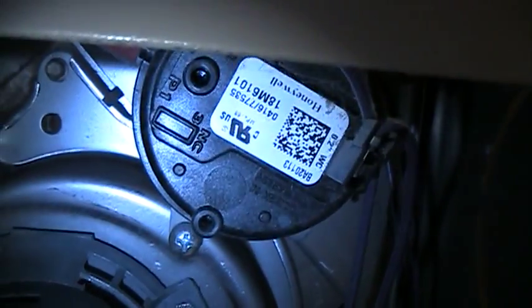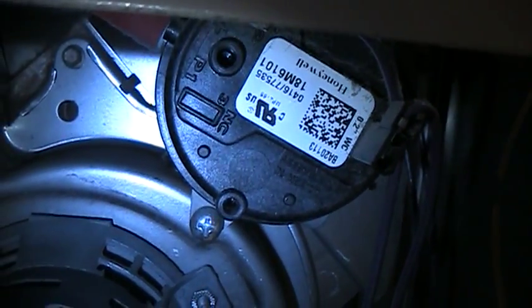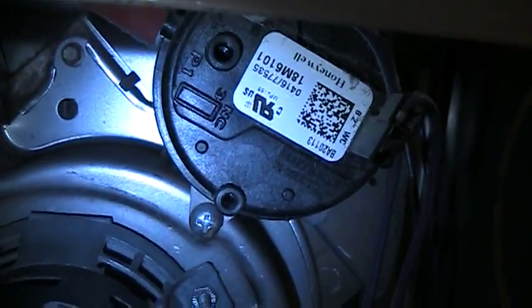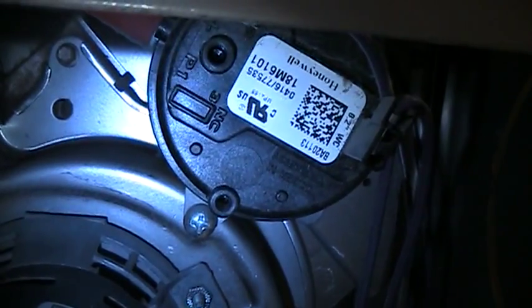Draft induction just came on. This is the last time. Pressure switch just verified that, makes a very soft click. All right. So. Draft inducer. Pressure switch. Hot surface igniter.